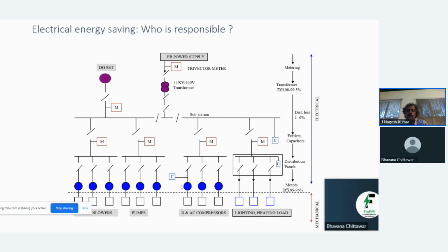Very rarely will you find replacement of an existing motor with IE3 quite economical - only where it's 24-hour operation, highly underloaded, or rewound many times. Then there can be a case, but it's still very difficult to prove in the field that there has been a tangible gain from going to IE3 motor. So very little option exists in the motor itself, transformer, or cable. So how is the electrical engineer going to save electrical energy?